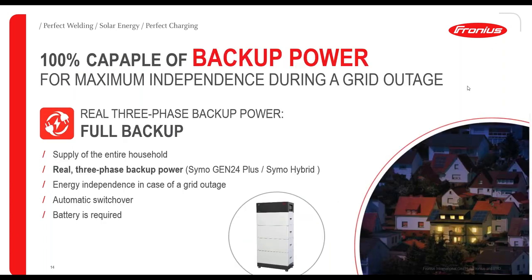What is very, very important when it comes to the GEN24 Plus device, or also Fronius hybrid inverters in general, is that we are 100% capable of backup power. That means we can guarantee the maximum independence during a grid outage situation with our two backup options. The first option is the full backup. That means we can provide real three-phase backup power, and the entire household would be supplied in case of such a grid outage situation. There is an automatic switchover.